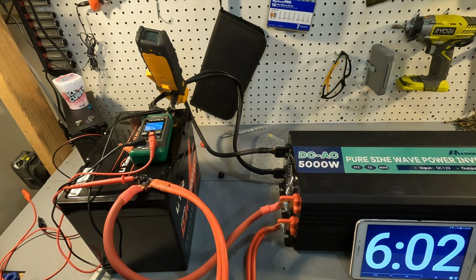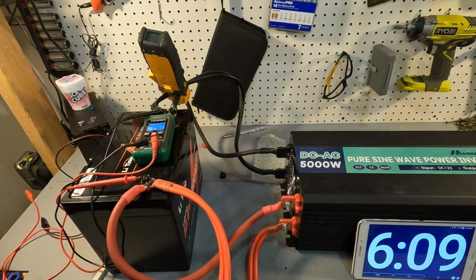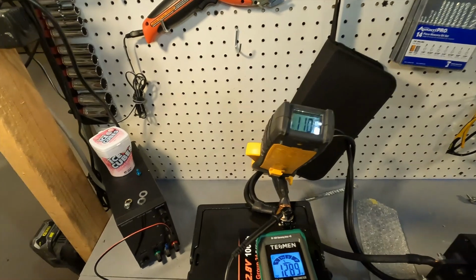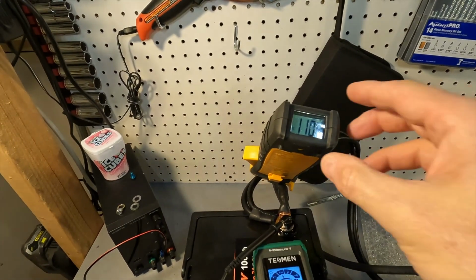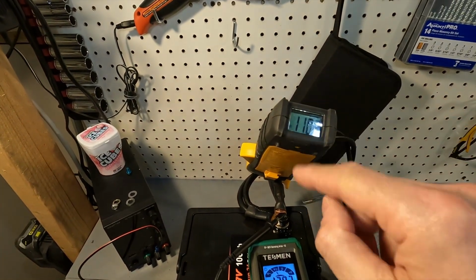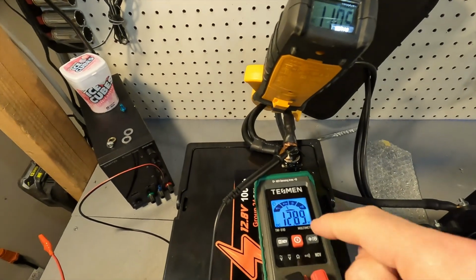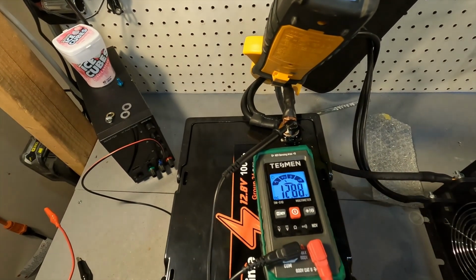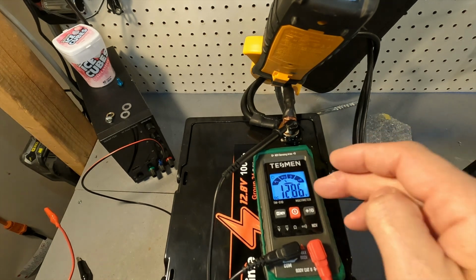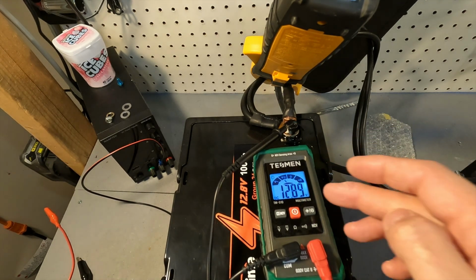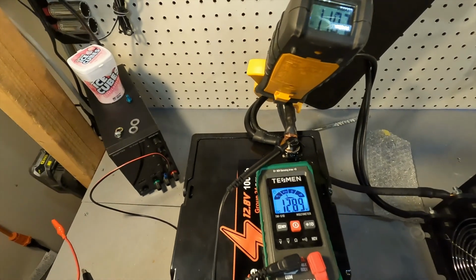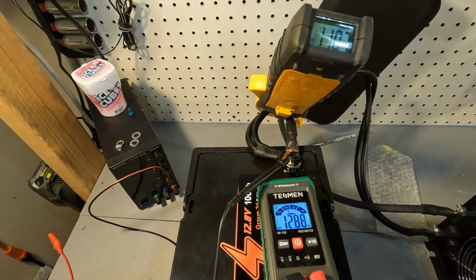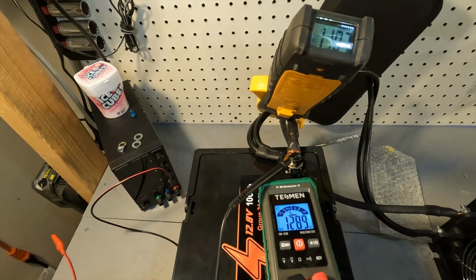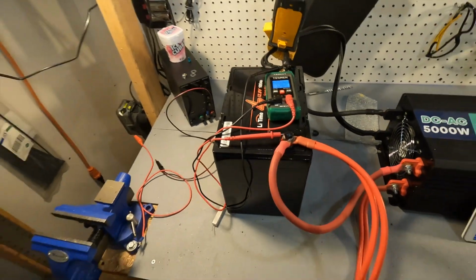Okay, well, it has been over 6 minutes now, you can see down here. Let's go ahead and look at the amperage and the battery. We still are running 110 amps, and the voltage is down to 12.88. But still, that is pretty good, it's only gone down maybe a tenth of a volt. So it is holding steady after 5 minutes, actually after 6.5 minutes.